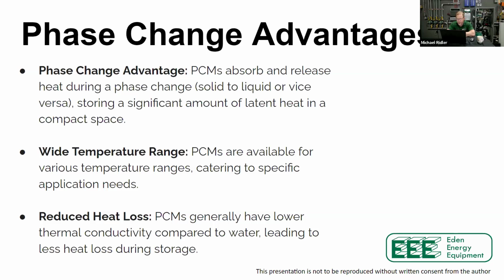Now we're seeing companies in Europe, whether in France, the Netherlands, Italy, or Scotland, developing phase change thermal batteries that can produce usable heat at as low as 43 degrees Celsius, or 120 degrees Fahrenheit. I've got an air-to-water heat pump sitting behind me, and for it to produce 120 degree water is very, very easy. I can still maintain a COP in excess of 2, which means that this technology, depending on which manufacturer is making the PCM material, is usable right now. That's the point of this discussion: to start talking about what we could do with it.